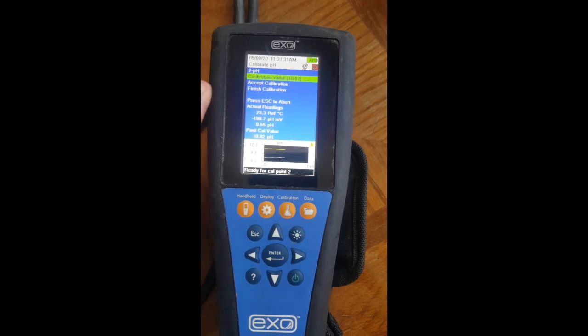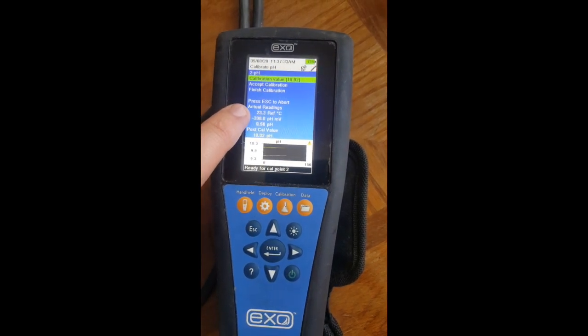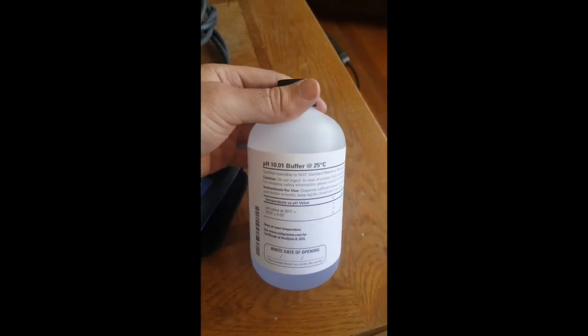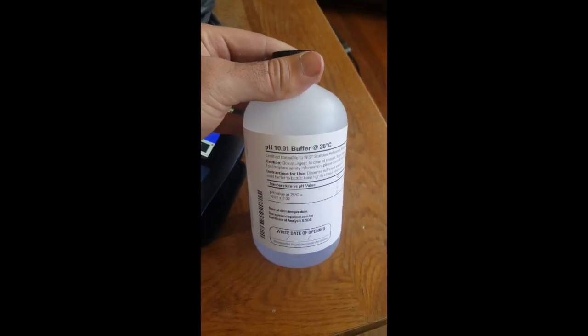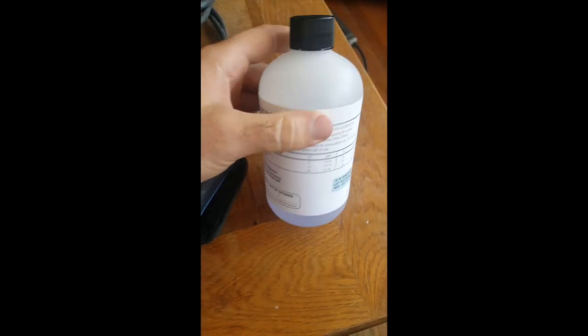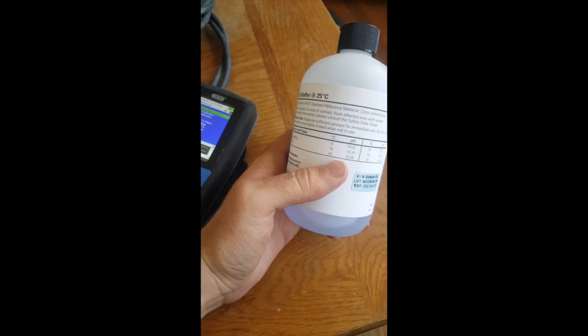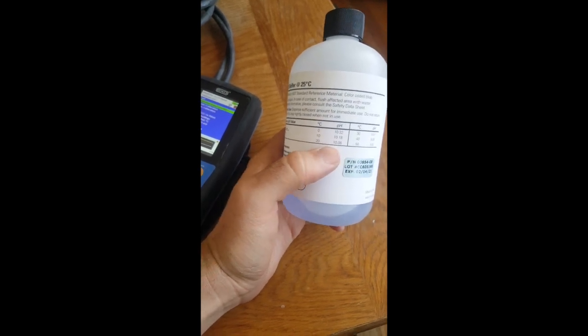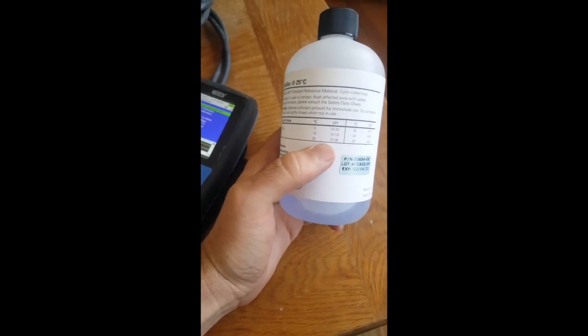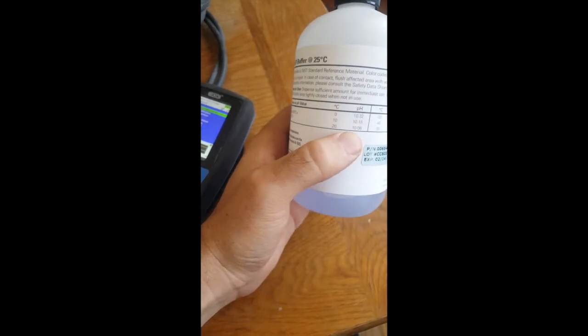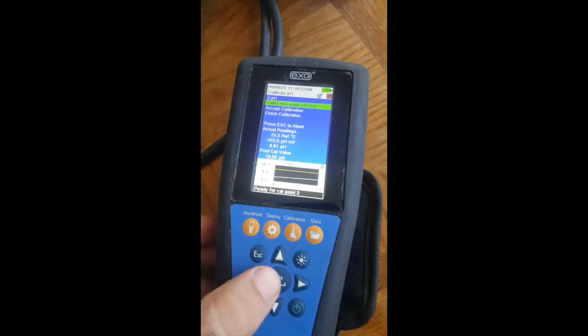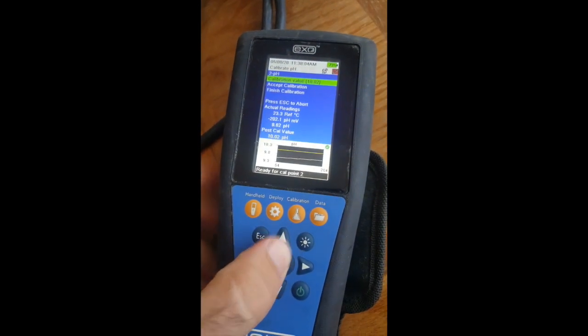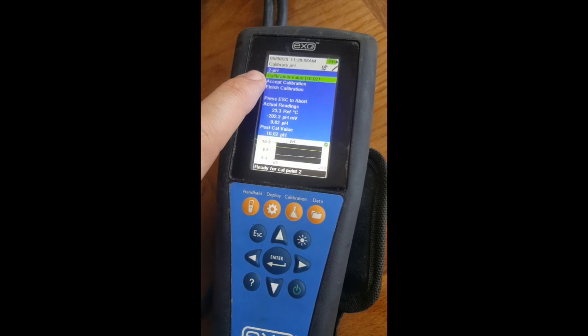Our reference temperature is 23 degrees Celsius. So just like the pH 7, we're going to look at the back of our bottle. At 25 degrees Celsius, this pH 10 buffer measures 10.01. Since we're at 23 degrees C, we need to adjust our pH properly. So I'm going to go 10.02. That's what I have set my calibration value at, 10.02.